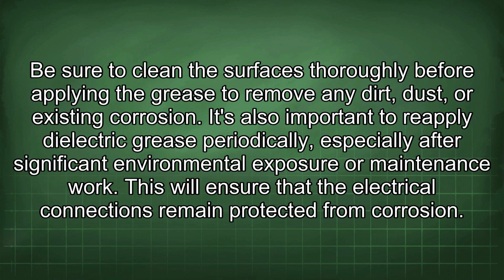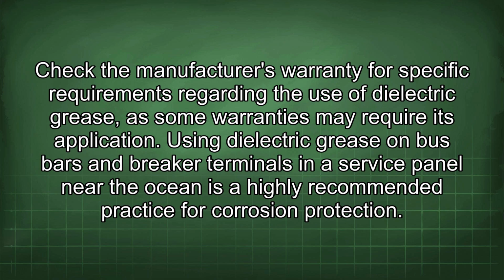It's also important to reapply dielectric grease periodically, especially after significant environmental exposure or maintenance work. This will ensure that the electrical connections remain protected from corrosion. Check the manufacturer's warranty for specific requirements regarding the use of dielectric grease, as some warranties may require its application.